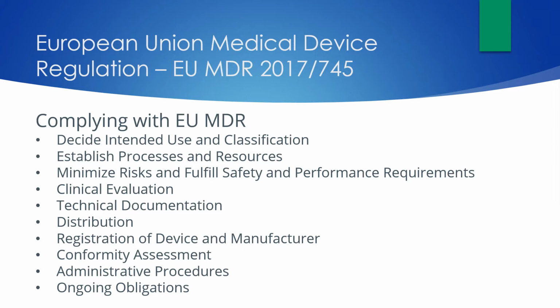For administrative procedures, finalization of the EU Declaration of Conformity and registration of the device allows for the device to be imported, marketed, distributed, and supplied for use and used within the European Union. And finally, ongoing obligations. These obligations include maintaining the risk management system, executing the post-market clinical follow-up activities, and keeping technical documents up to date.